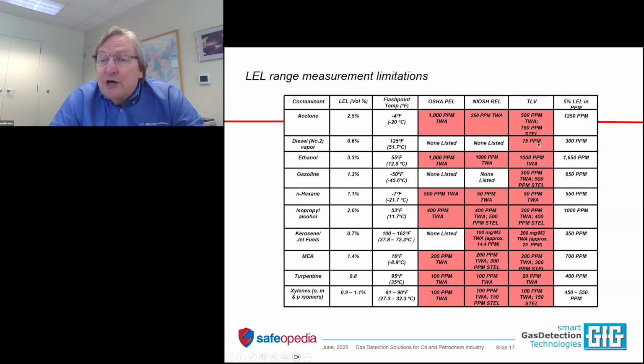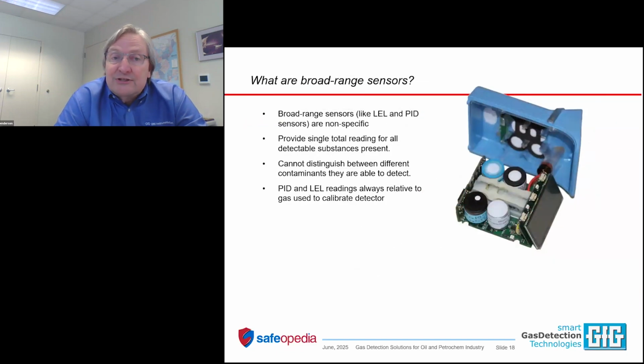For diesel, we'll be talking about the diesel TLV in a few slides here. The TLV is 15 parts per million. 5% LEL is 300 parts per million. That means even if you set the alarm at 5% LEL, even if the sensor does a good job of detecting the diesel vapor, you're exceeding the toxic exposure limit by 20 times if that's where you're setting the alarm. So that's really not acceptable, and that's why for VOCs, because of these toxicity issues, you really do need to include a PID sensor.